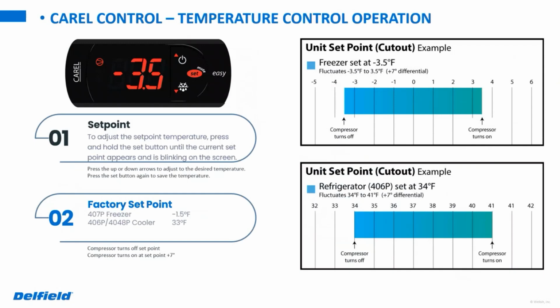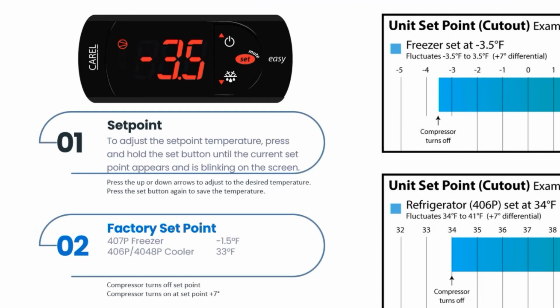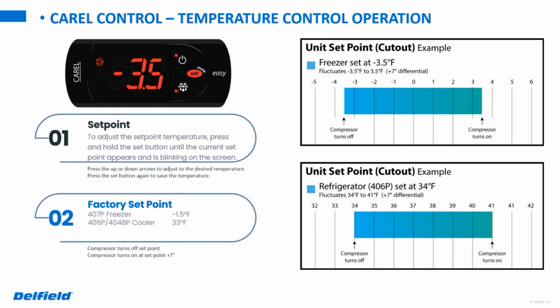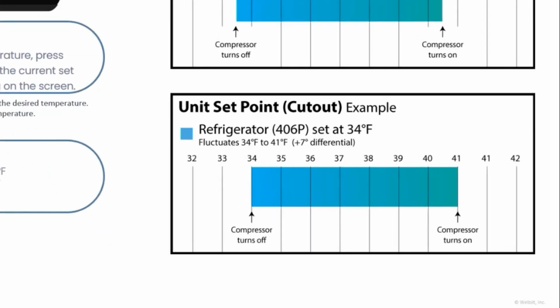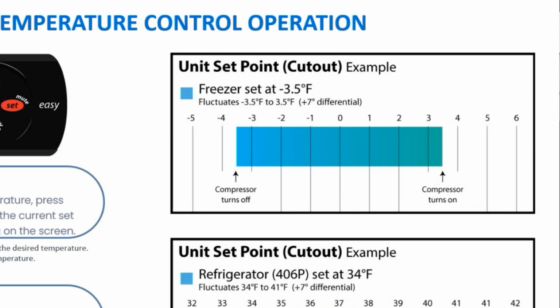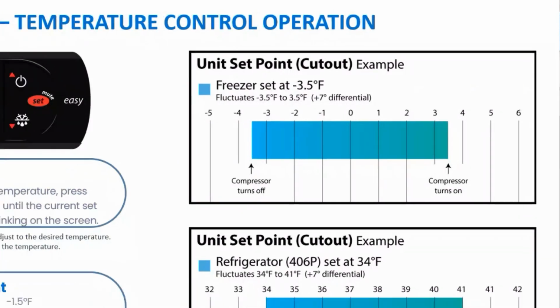As far as the operation of the temperature control and setting box temp and things of that nature, the set point on these is where the unit will cycle off. So on a cooler, we normally set those at around 33, 34 degrees. And then the freezer, I usually tell people set them around 0 to -2, somewhere in that particular area. So with that, the differential on that's going to be 7 degrees. So when that unit cycles off, and we'll use the cooler as an example, when the cooler cycles off at 33 degrees, it's going to come back on at 40 degrees. Same thing with the freezer. If it's set at -2, it's going to come back on at 5 above 0.